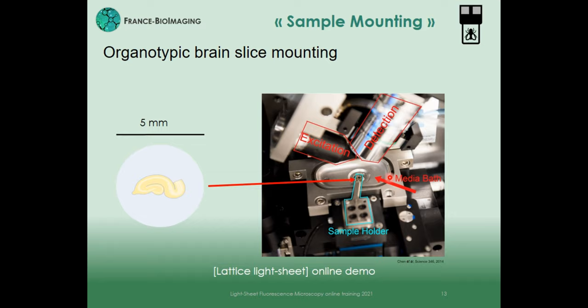The sample holder with the brain slice is screwed onto the sample piezo stage for 3D acquisition, which is also mounted on an XYZ translation system for sample positioning. The sample is immersed and can be perfused; the sample chamber contains approximately 7 millilitres of liquid. Its temperature, as well as the temperature of the objectives, can be controlled. Due to the limited space between the objectives, the sample translation volume is restricted to approximately ±1 mm in the horizontal plane and ±0.5 mm in the vertical direction.